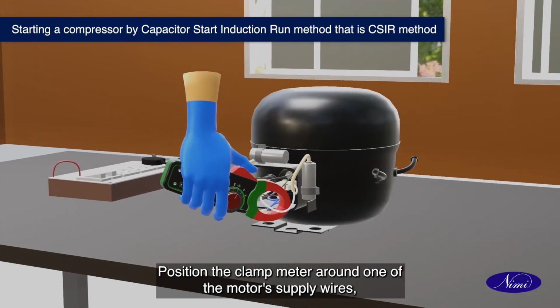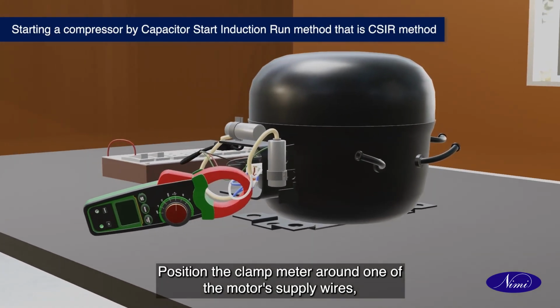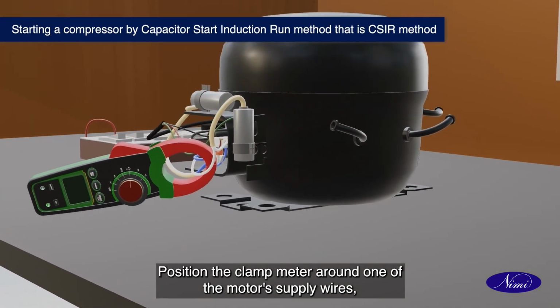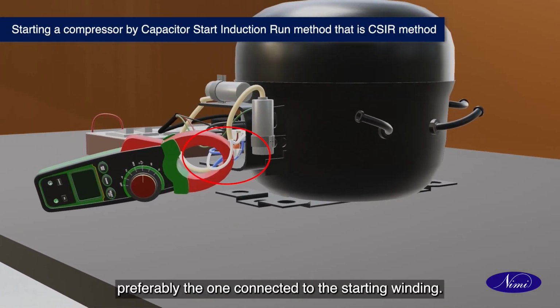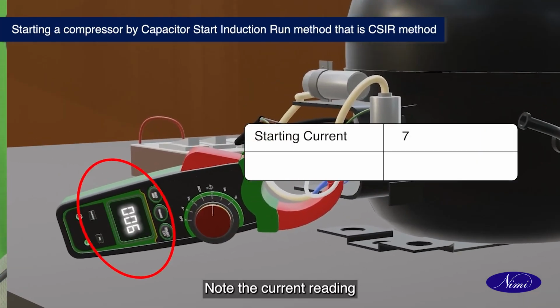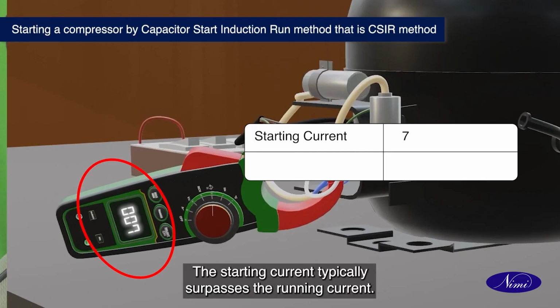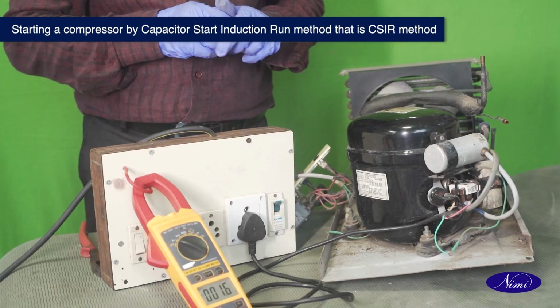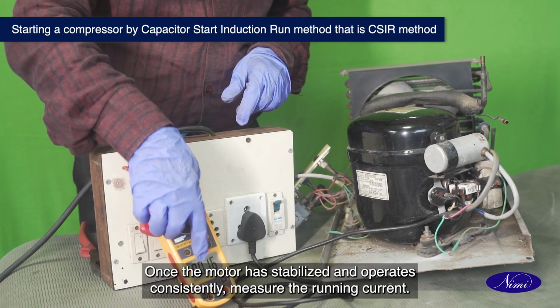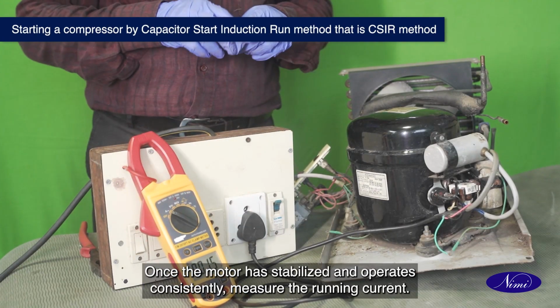Position the clamp meter around one of the motor's supply wires, preferably the one connected to the starting winding. Note the current reading when the motor initiates. In CSIR motors, the starting current typically surpasses the running current. Once the motor has stabilized and operates consistently, measure the running current.